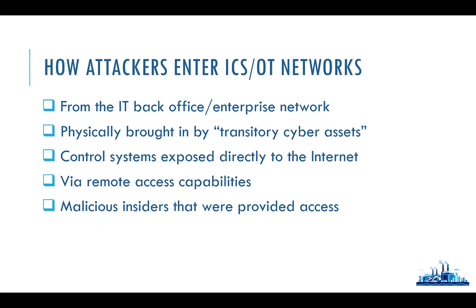There are a couple of main ways that attackers can get into control system environments. One of the more common ways — like we saw in the Colonial Pipeline breach — is attackers from a ransomware group got an employee in the back office to click on a link or open a malicious attachment, infect their system, and that infection started spreading into the control system network. That's a very common way: start on the IT network and then use those connections to move into the OT network.